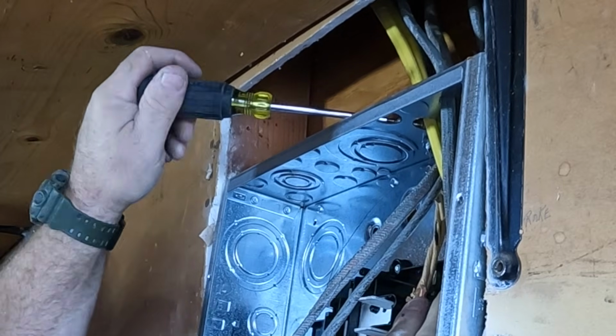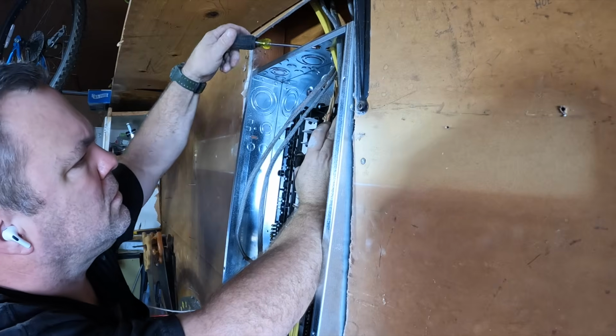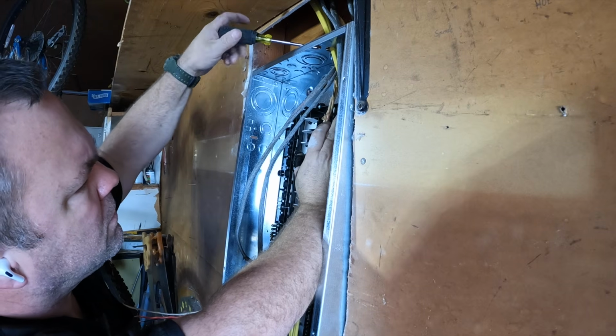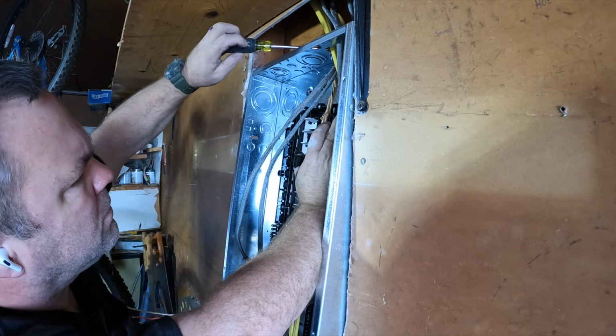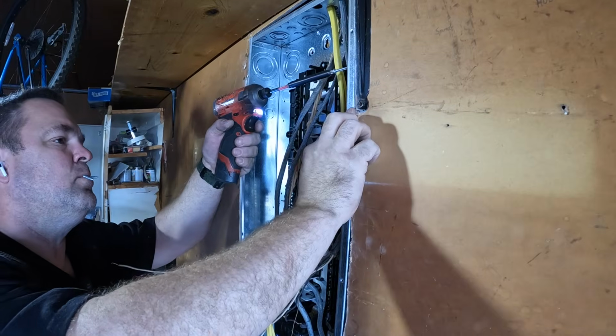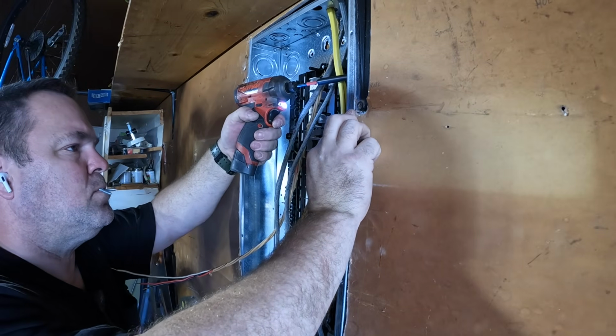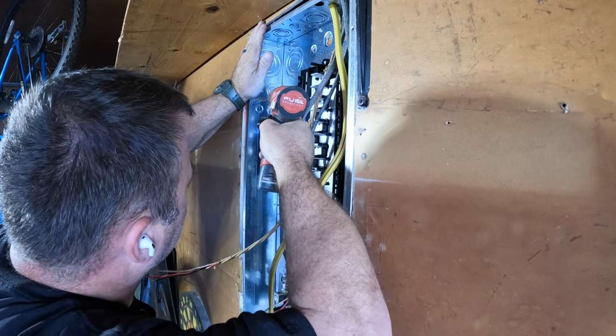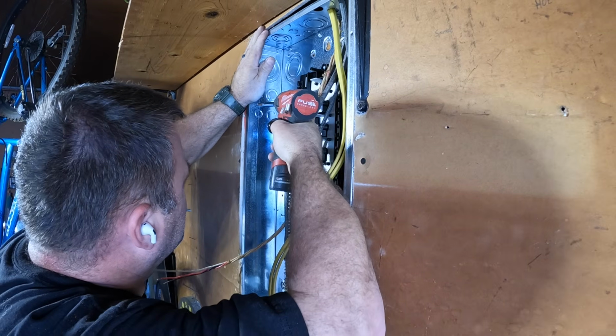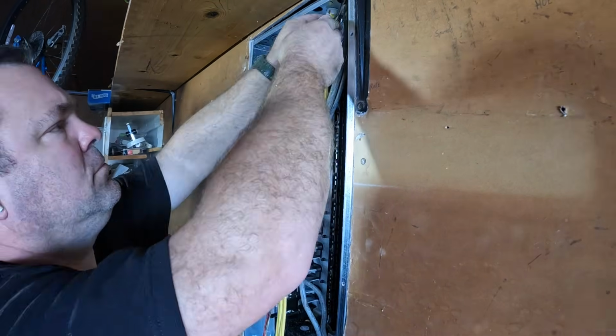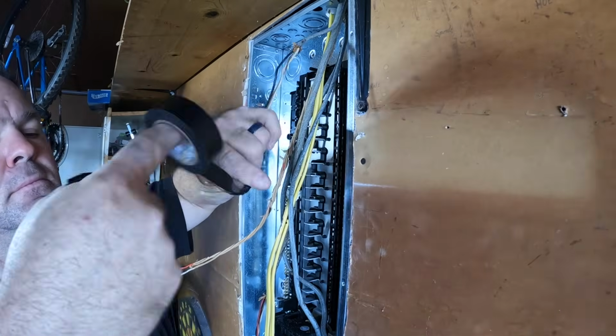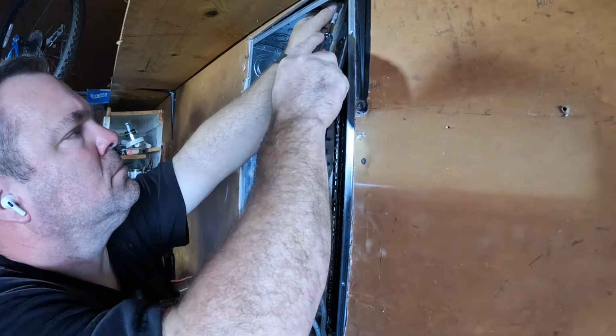And so once I get these cables inside the enclosure, I could push it up. This is what's known as a flush mount installation, where it's flush with the finished drywall. I come back with some number 10 1-inch sheet metal screws, attach it to the studs, and pretty soon here we'll be ready to start terminating conductors and installing circuit breakers.